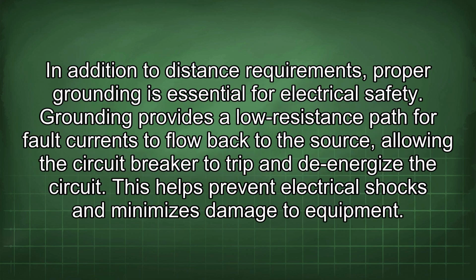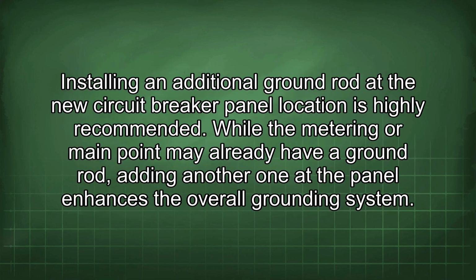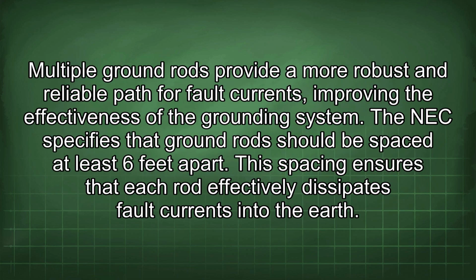In addition to distance requirements, proper grounding is essential for electrical safety. Grounding provides a low-resistance path for fault currents to flow back to the source, allowing the circuit breaker to trip and de-energize the circuit. This helps prevent electrical shocks and minimizes damage to equipment. Installing an additional ground rod at the new circuit breaker panel location is highly recommended. While the metering or main point may already have a ground rod, adding another one at the panel enhances the overall grounding system. Multiple ground rods provide a more robust and reliable path for fault currents, improving the effectiveness of the grounding system.